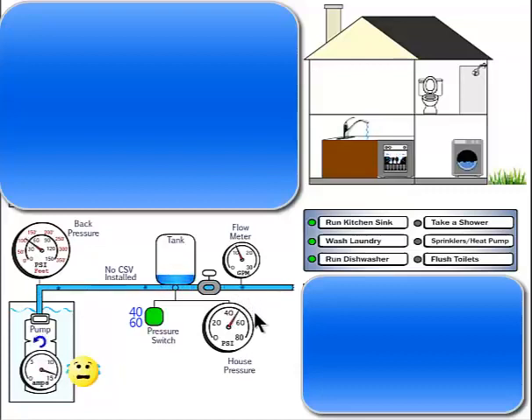The larger the pressure tank, the slower the cycles. But the larger the tank, the longer you will experience low pressure in the shower before the pump is started and stronger pressure is achieved.